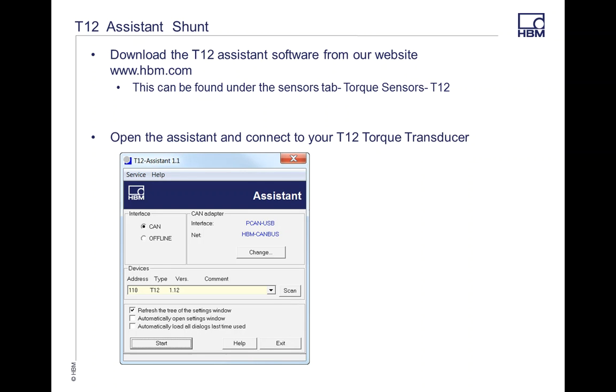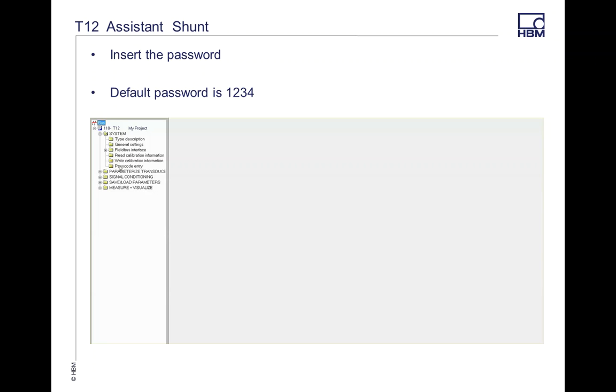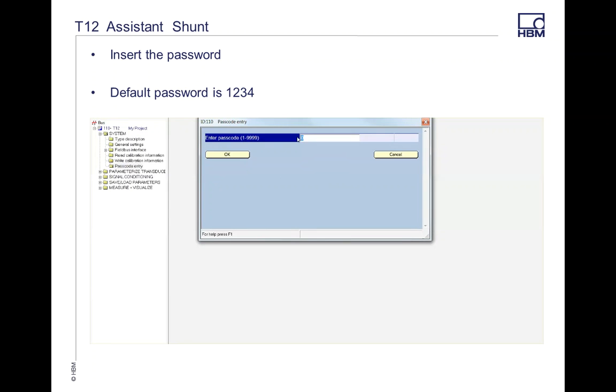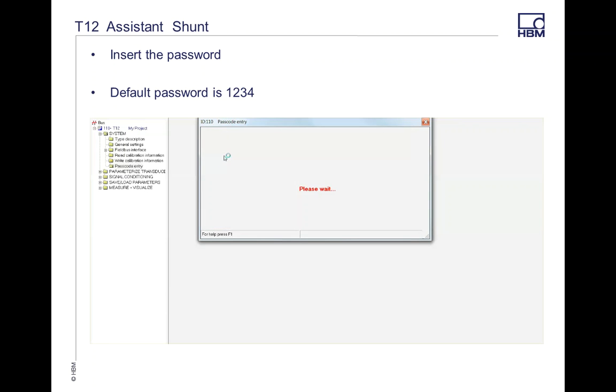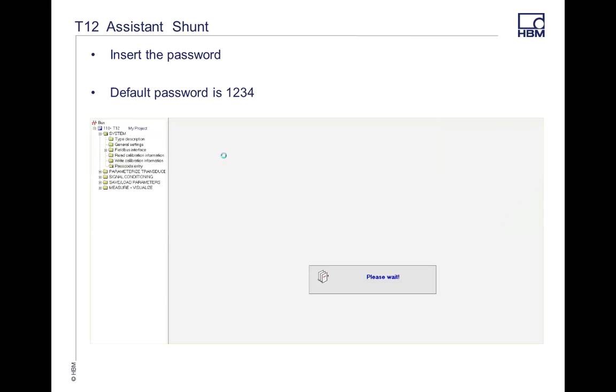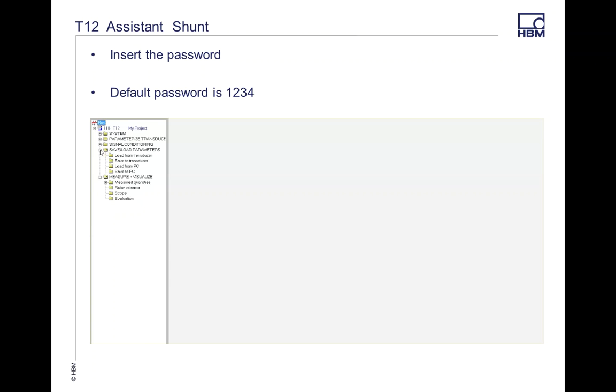To open the assistant, there are a couple of different ways to do it. There's an online mode, which goes right through CAN, or there's an offline mode where you can get everything set up at your desk. So you're going to scan and connect in through CAN. The initial password on all of the T12s is 1234. I want to show you a quick video on this. When you go into your password, you put in 1234 and hit OK. It's going to come up with a please wait. You also have to hit this again, and you're looking for these 3 little pieces of paper that flip. That's actually getting into your transducer itself. So keep that in mind as you go through the T12 assistant.